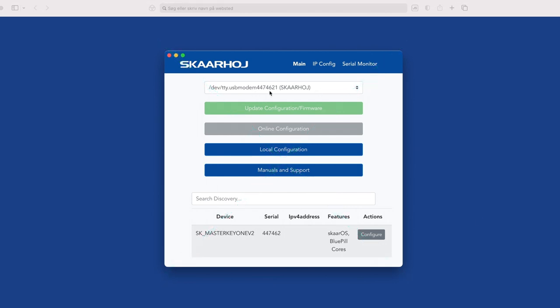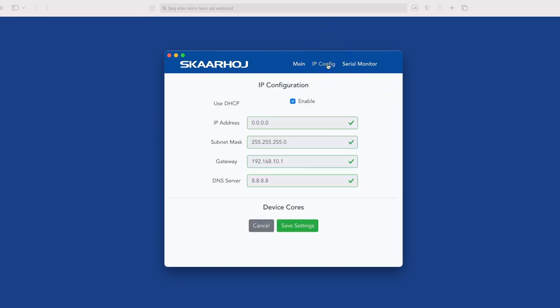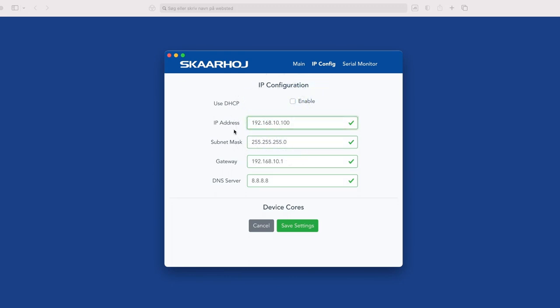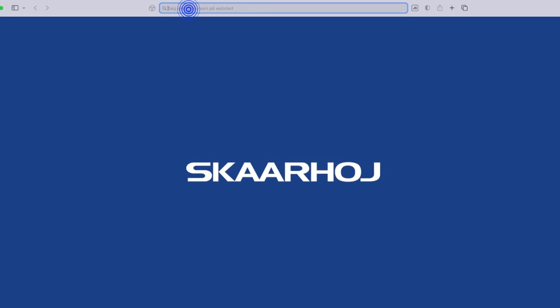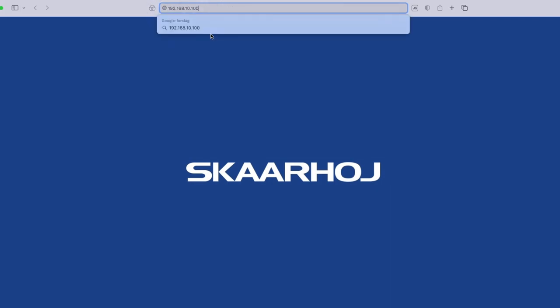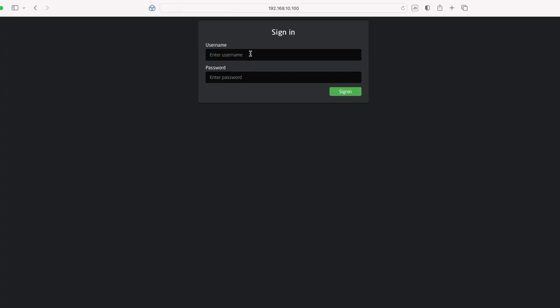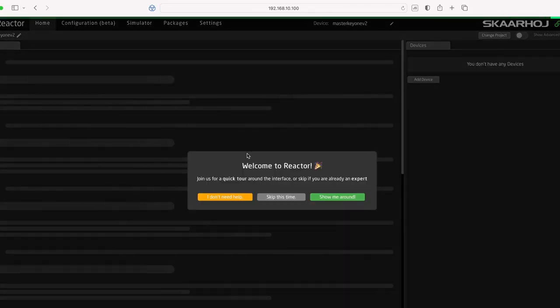In the top of the window, we see that there is a USB connection. Click IP Config, deselect 'Use DHCP', and enter a static IP address, subnet mask, and gateway. Click 'Save Settings' and wait a moment while it updates. That's it — we're done. Now we can open a web browser and enter the static IP address. Here we see Reactor, the configuration manager for Bluepill.